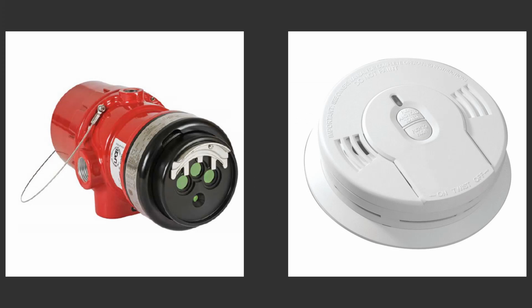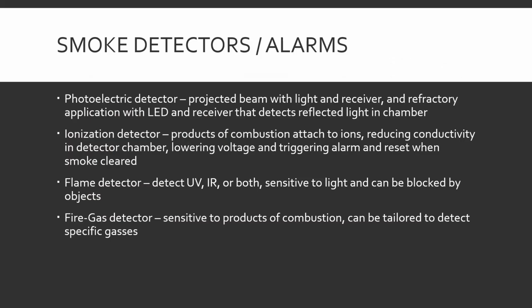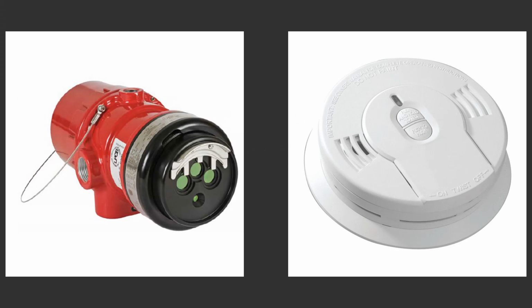The guy on the left is our IR, our light sensing one, the little camera guy I was talking about. The photosensitive one. And you can see on the front there, those are the little cameras. That's what's looking for the flames or the UV light. And then over on the right side, that is the ionization detector. That's the one in your house. Smoke gets in there, steam gets in there, it goes off. That sucks. Pull the battery even though you shouldn't. Smoke goes away, put the battery back in. Everyone's happy.